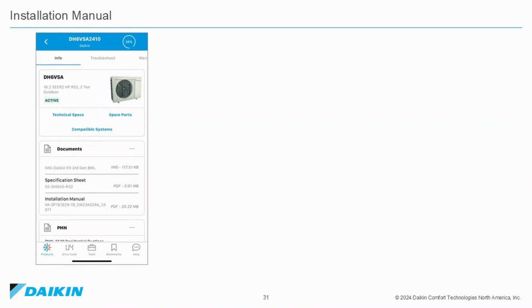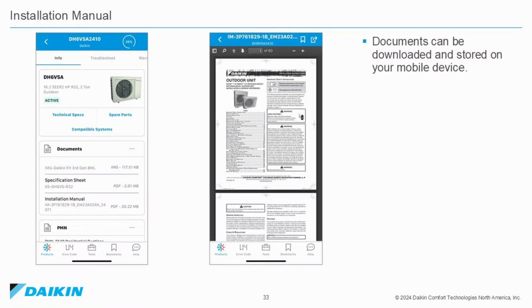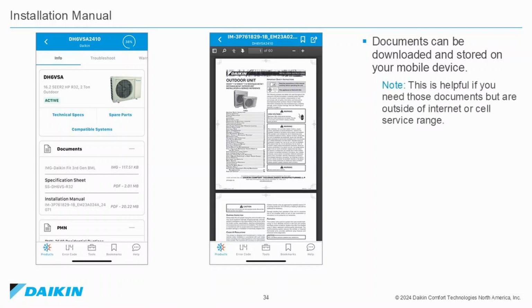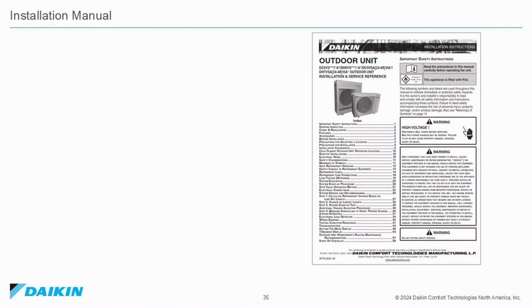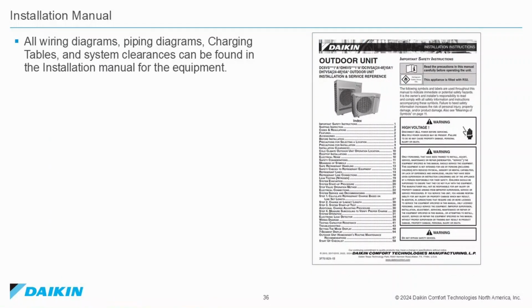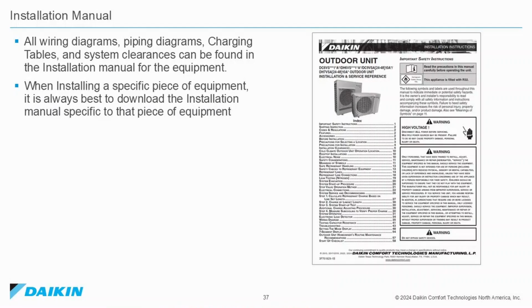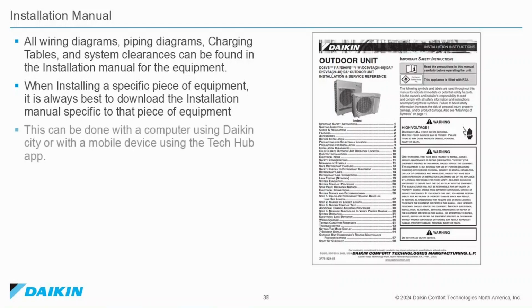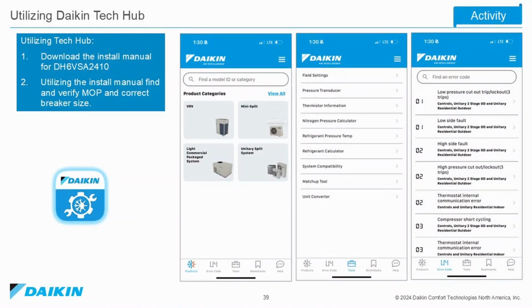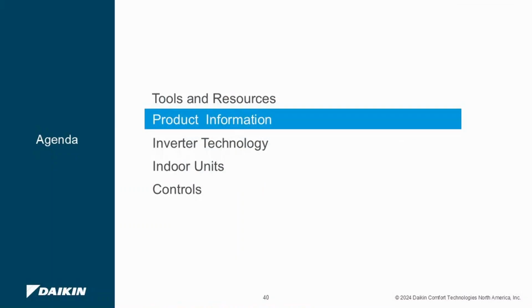Installation Manual and System Information. These documents can be downloaded and stored on your mobile device. This is helpful if you need those documents but you are outside of internet or cell service range. All wiring diagrams, piping diagrams, charging tables, and system clearances can be found in the installation manual for the equipment. When installing a specific piece of equipment, it's always best to download the installation manual specific to that piece of equipment. This can be done with a computer using Daikin City or on a mobile device using the Tech Hub app. Product information.